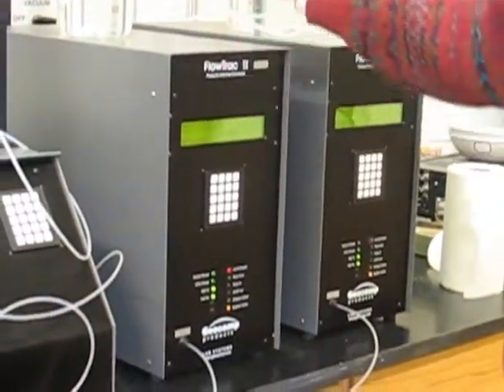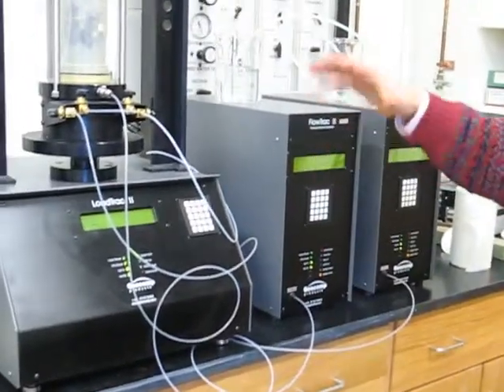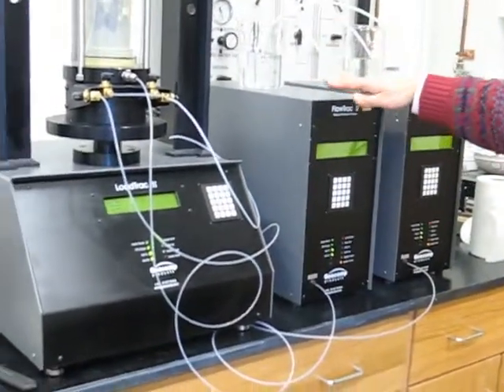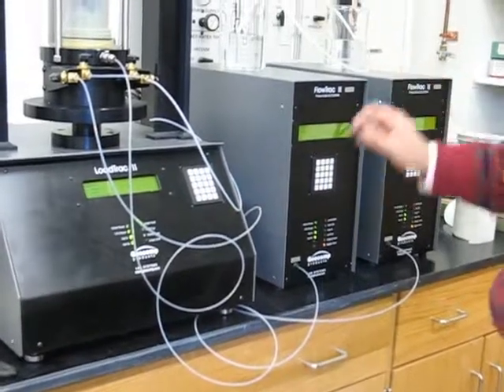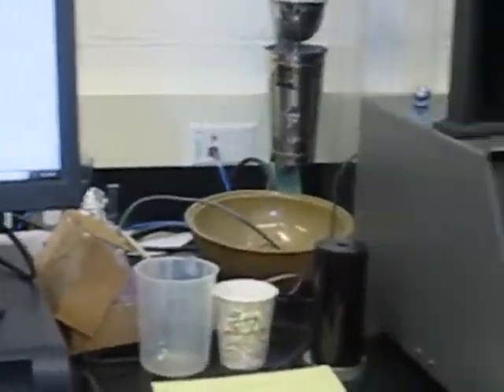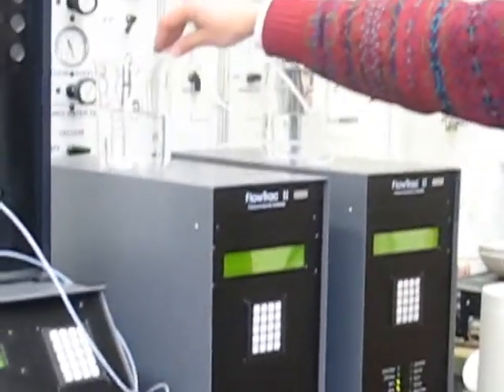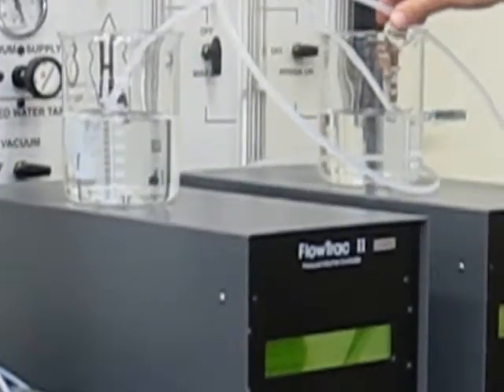Now the next window that comes out is initialize flow pump. You say yes. And once you say yes, the flow pump automatically closes and opens valves, empties the water and fills it to the capacity that you specify. In this example, we have 90% and 75% here. So I'm going to say yes, and it will automatically empty. It was already empty, so now it's filling the pumps with water until it gets to the capacity.